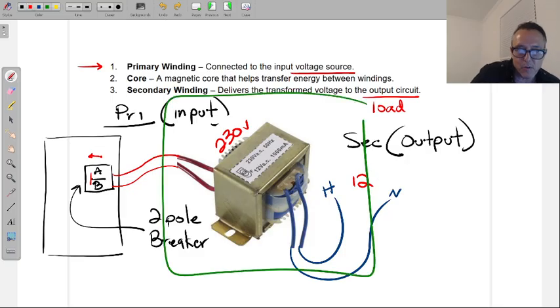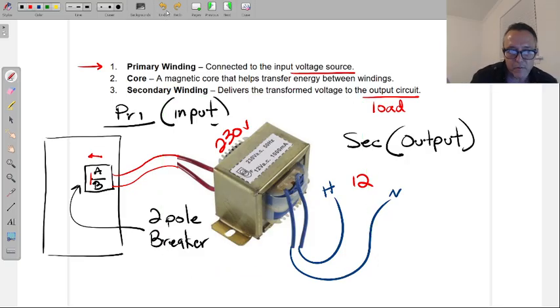This is not a doorbell transformer - maybe that was the confusion. This one specifically isn't a doorbell transformer, only because I've never seen a doorbell transformer require 230 incoming voltage. Usually a doorbell transformer, since it's used in a house, is going to have 120 on the primary side.